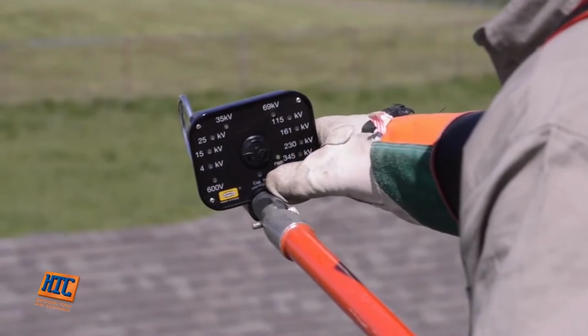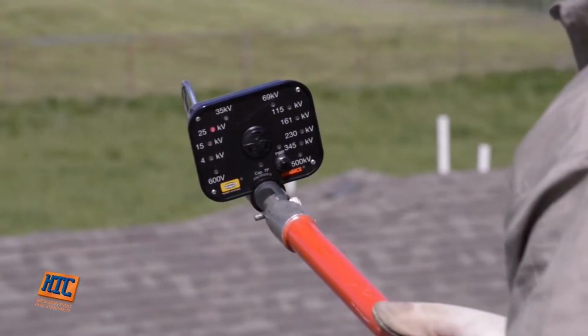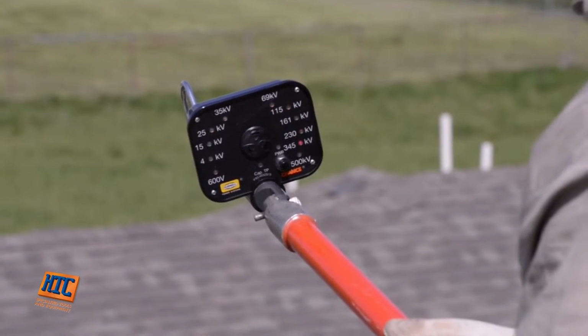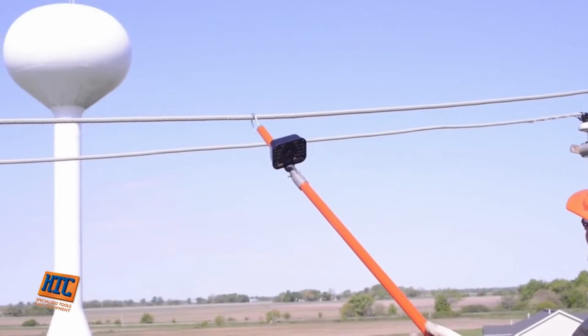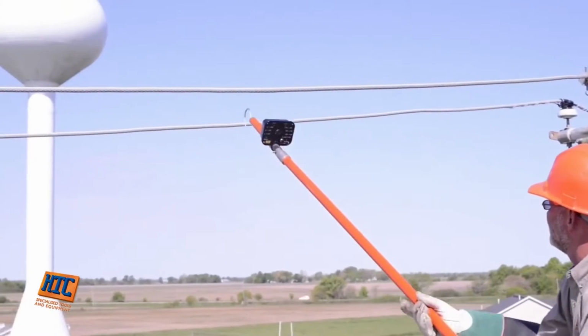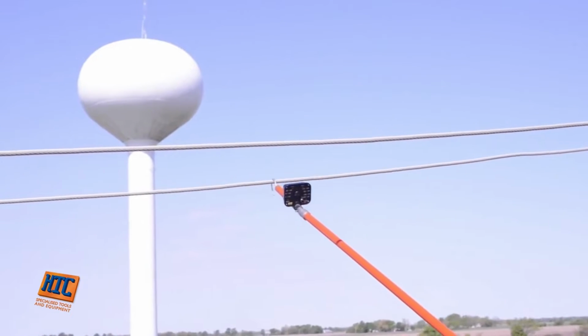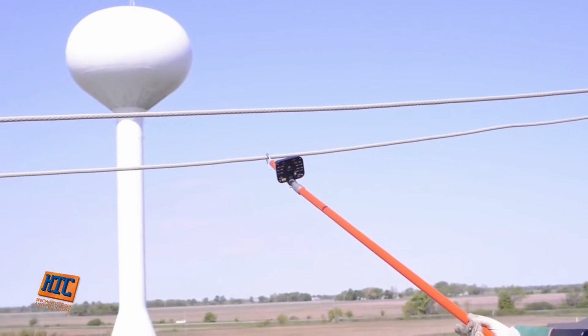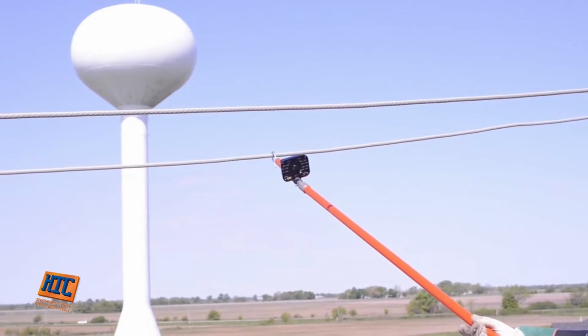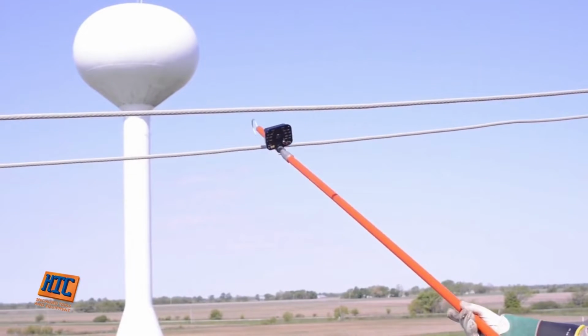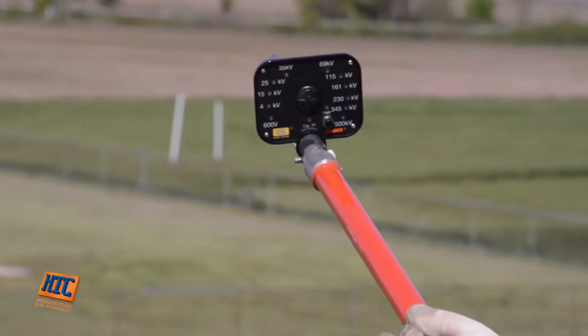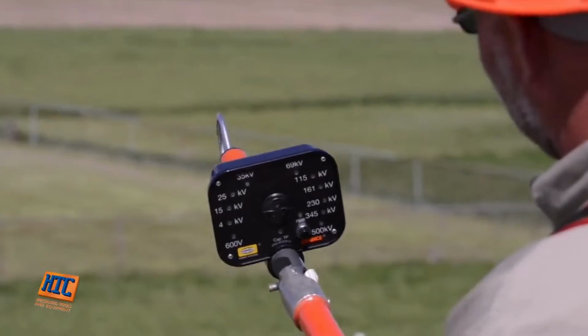Mounted on a universal hot stick of appropriate length for the voltage being worked, turn on the RV and touch its hook to each conductor. Notice that when the RV senses the electric field, it emits an audible beeping sound and displays the appropriate voltage class for the circuit, in this case 4 kV. Had the circuit been de-energized, no LED for a voltage class would be blinking.